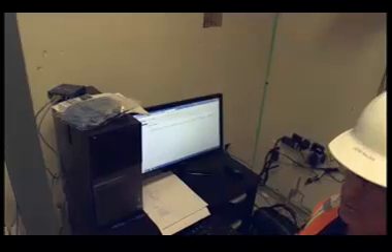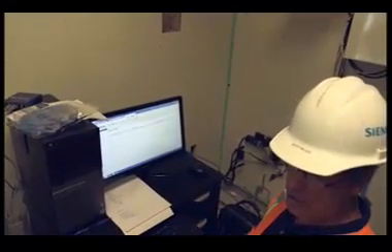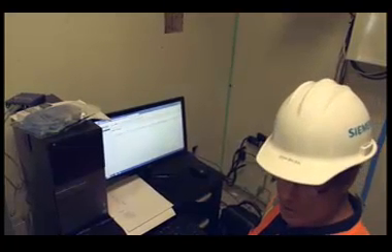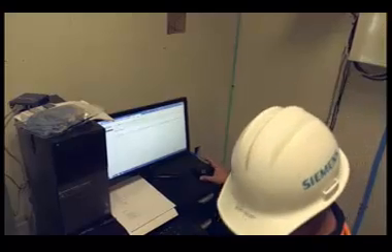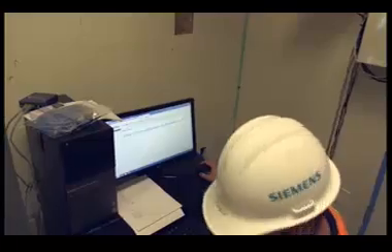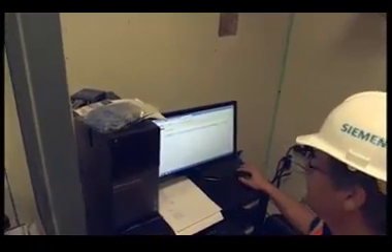So in that minimum position to its maximum position, trainers told me that those outside air dampers will not go any further open than 50%. Are these the same dampers that in case of a fire they'll shut down all the air? Right. Okay. Yeah, because you don't want outside air coming in. Okay, so we'll kind of review that in the next thing with the fire alarm going.